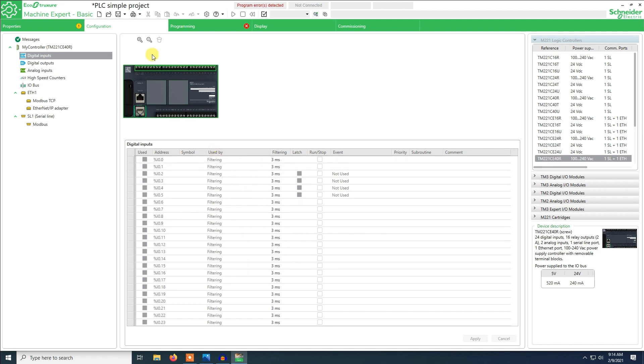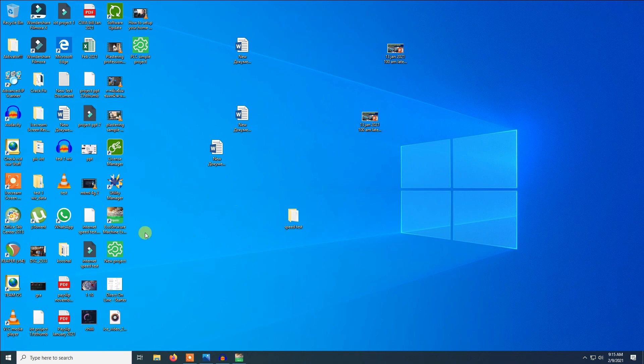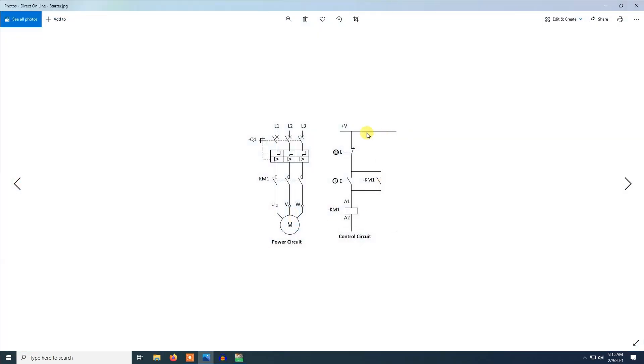There are 24 inputs. For the program, I'm going to start a simple program. I will just do a direct online: a normally closed switch, a normally open switch, and this is a contactor. This is an auxiliary contact of the contactor KM1. This is an overload, and this is the contactor, which connects to the three-phase motor, and here you have the incoming three-phase supply.